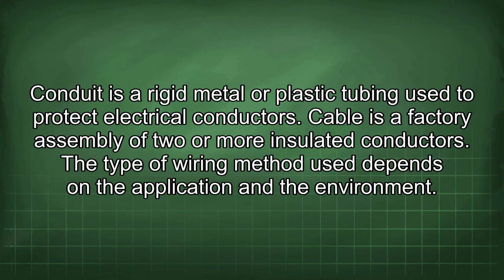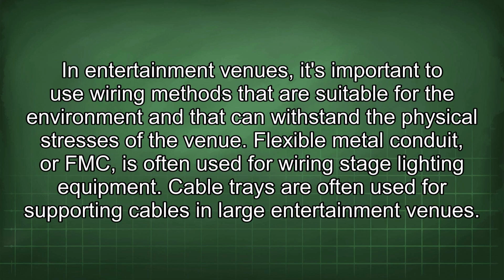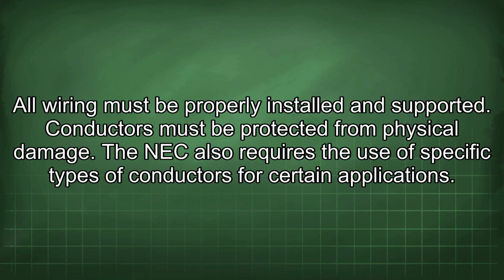The type of wiring method used depends on the application and the environment. In entertainment venues, it's important to use wiring methods that are suitable for the environment and that can withstand the physical stresses of the venue. Flexible metal conduit, or FMC, is often used for wiring stage lighting equipment. Cable trays are often used for supporting cables in large entertainment venues. All wiring must be properly installed and supported. Conductors must be protected from physical damage.